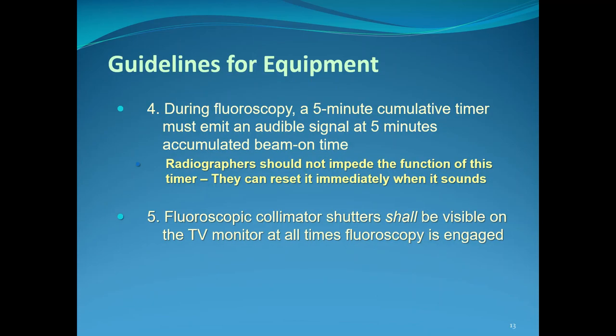During fluoroscopy, a five-minute cumulative timer must emit an audible signal at five minutes of accumulated beam-on time. This is not a running clock from when the exam starts — it's a timer that counts only while the beam is on. Radiographers should not impede the function of the timer, but they can reset it. It is the radiographer's responsibility to alert the radiologist when the five-minute cumulative fluoro time has been reached, as the radiologist may be focused on the exam. Let them know, and they'll instruct you to reset the timer or make another decision.